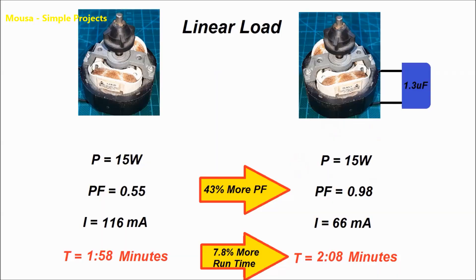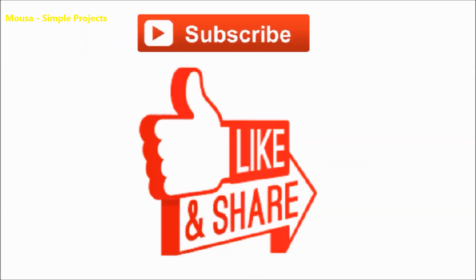Increasing the inductive load power factor by 43% increases the inverter runtime by 7.8%. So I can see a significant change in the inverter runtime before and after power factor correction. Please like this video and subscribe to my channel — thanks for watching.